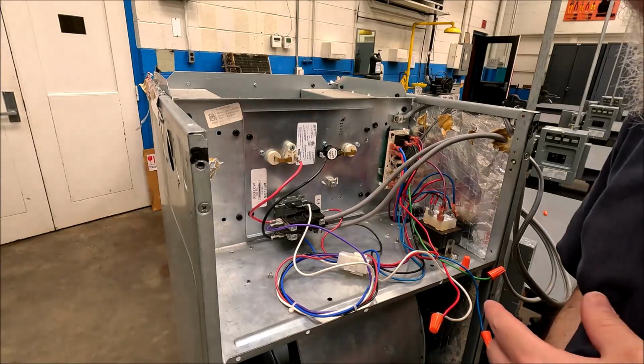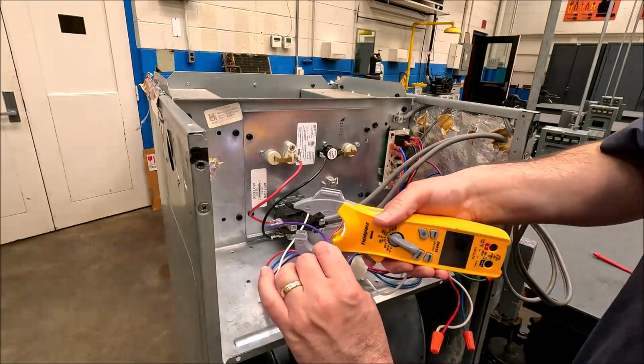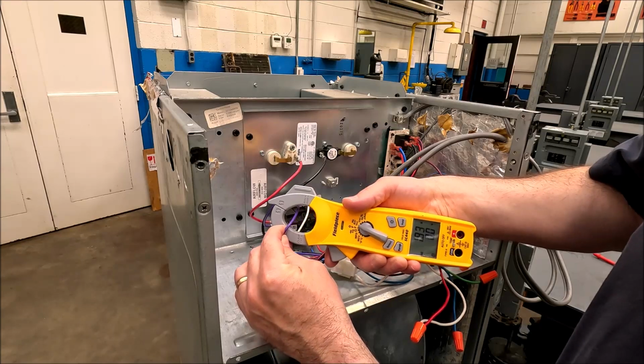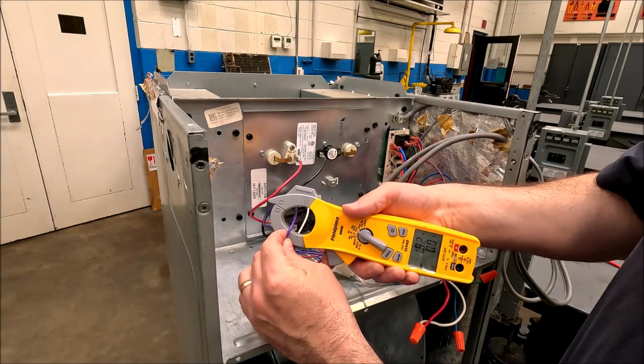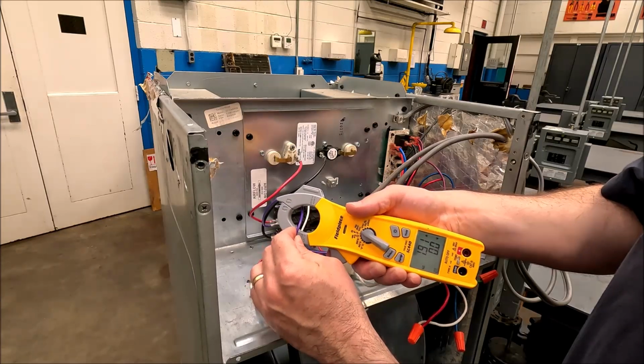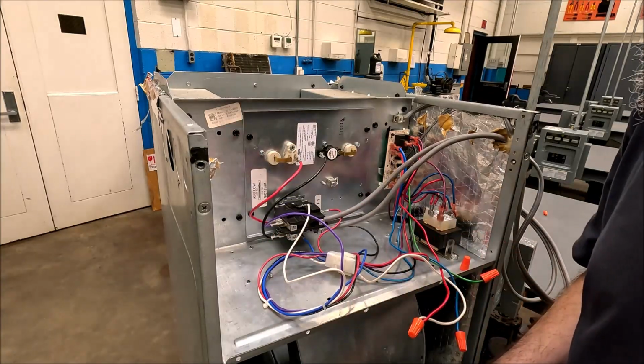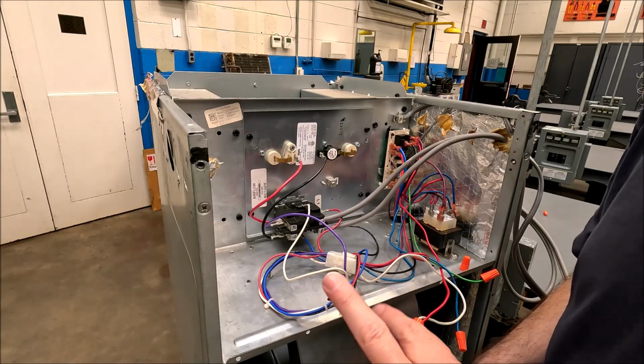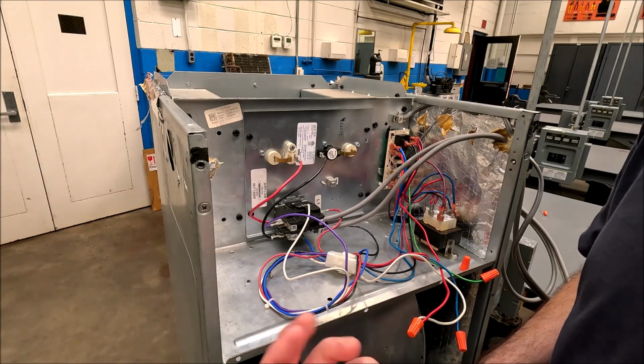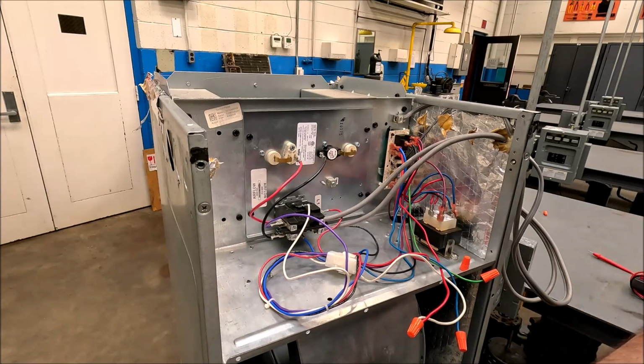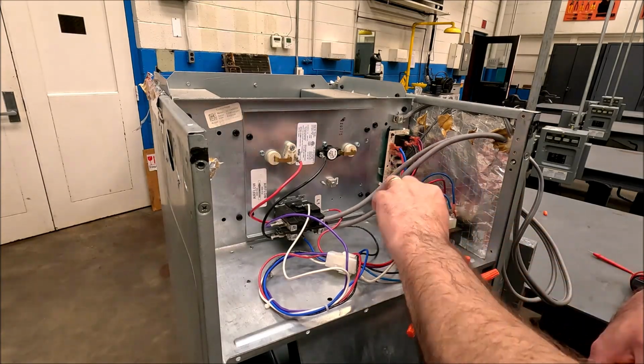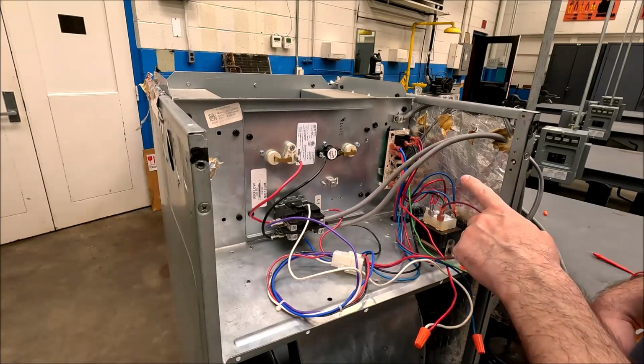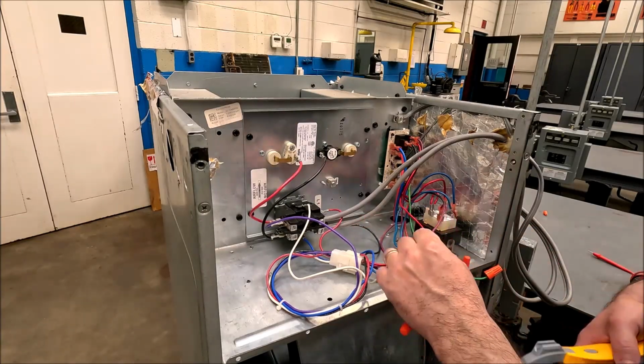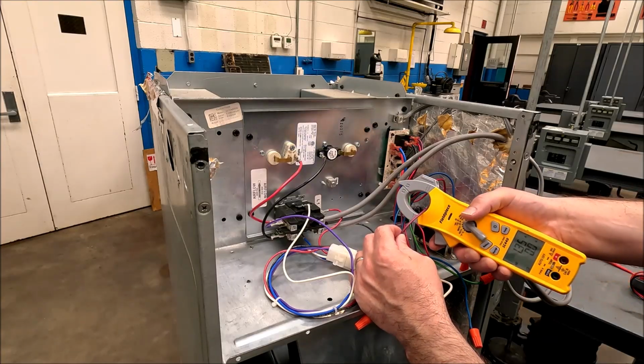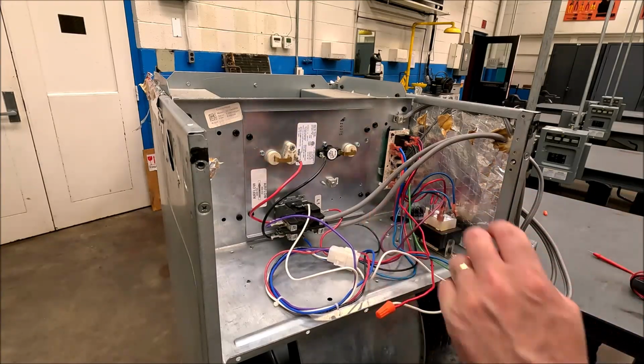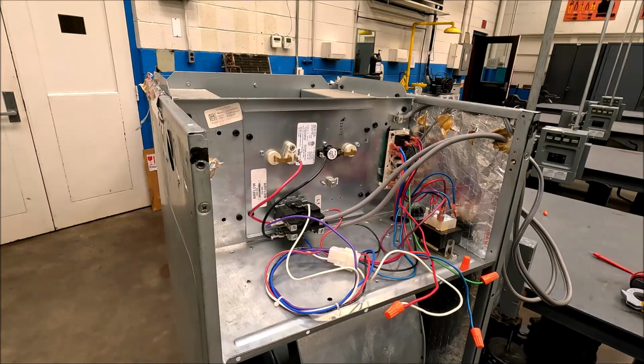Now, if I check off of this purple wire, 1.92 amps, but you have to remember this purple wire is not the other side of power. So in a PSC motor, we've got 2 windings and they're each gonna pull their own amperage. They're like 2 individual loads. So for me, I know that this purple wire over here, coming back to the black wire, which goes back to my L2 side, that is my other side of power. 1.9.